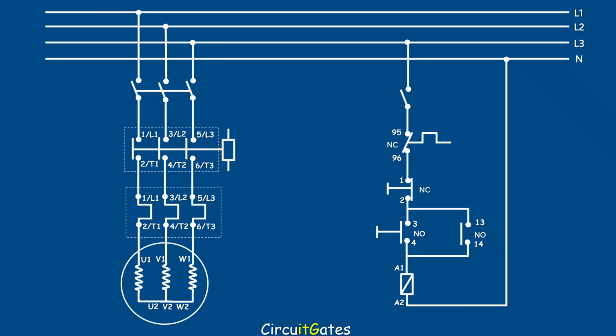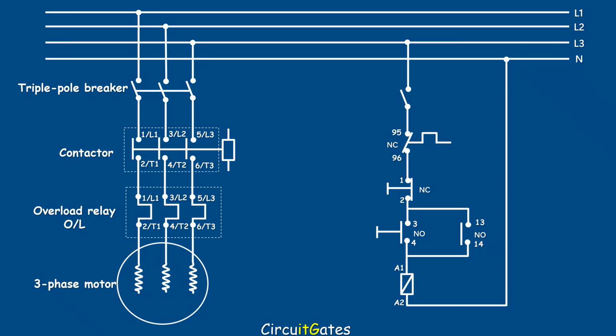The two circuit diagrams shown here show the power circuit and the control circuit of a direct online starter. On the power circuit, we have a triple pole circuit breaker, followed by a contactor, an overload relay, and an electric motor wired either in star or in delta connection. In a star connection, 3 live conductors are each connected to the coils of the electric motor, and the outlets from the coils are joined together.